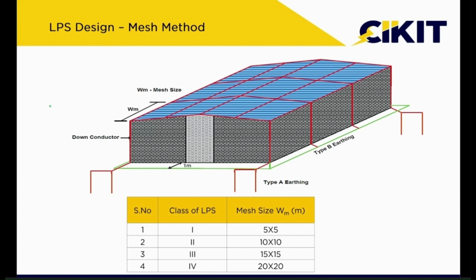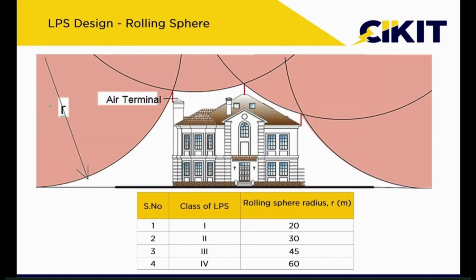And the third method, and the most commonly used method for designing the lightning protection system, is the rolling sphere method. Here, we will be rolling an imaginary sphere over the structure to be protected. And in this method also, the radius of the sphere depends upon the levels of protection. For level 1, the radius of the sphere will be 20 meters, whereas for level 4, the radius of the sphere will be 60 meters. So if you observe, in all the three methodologies, the level of protection plays an important role.